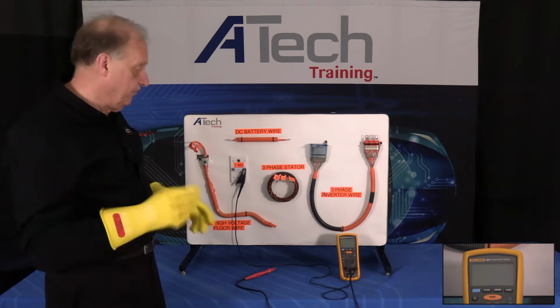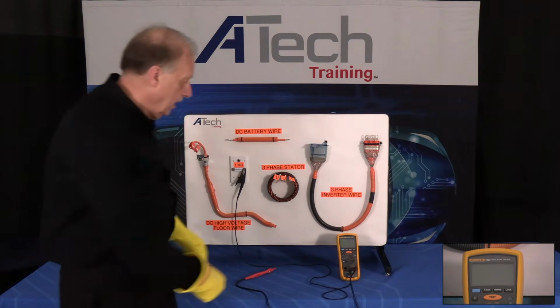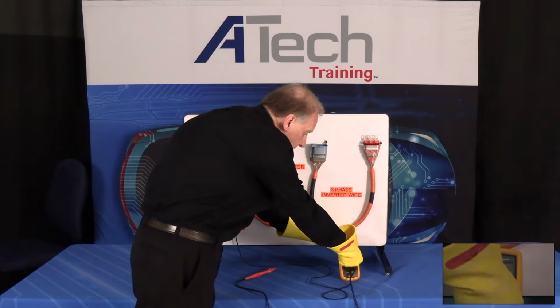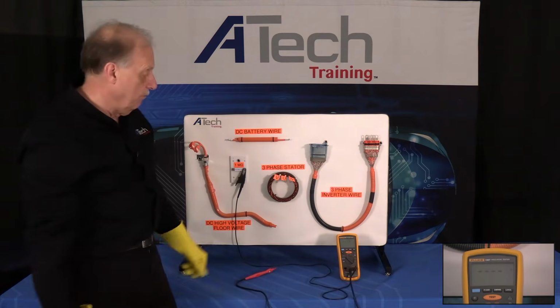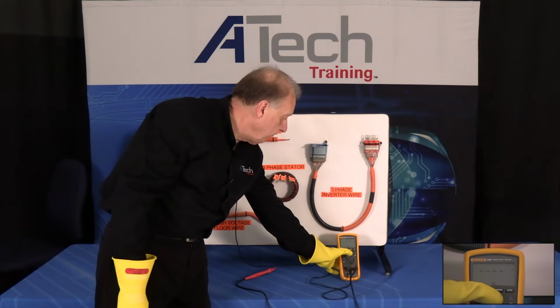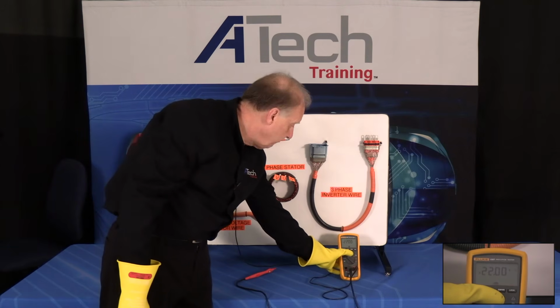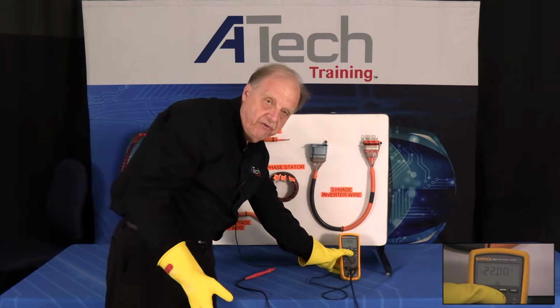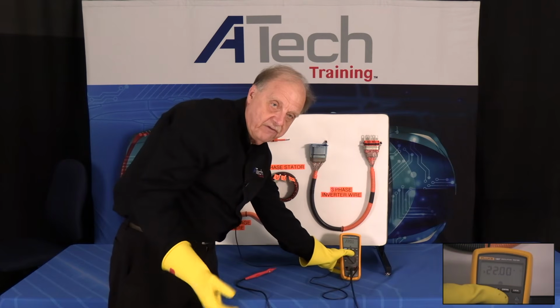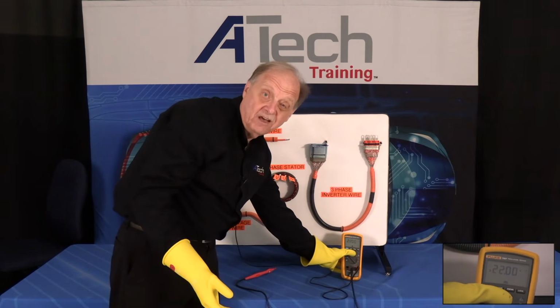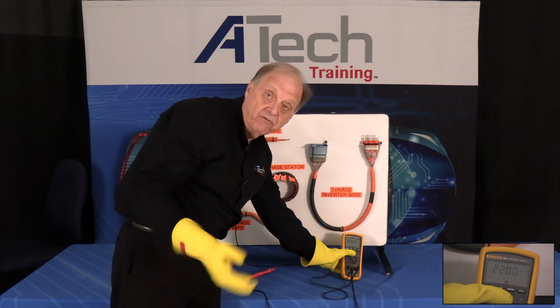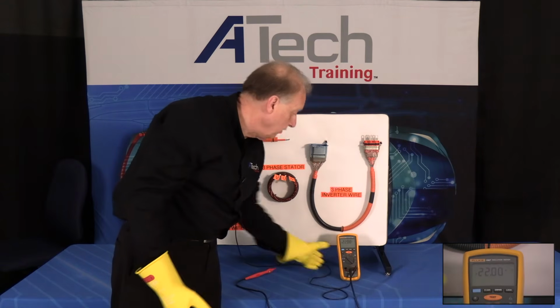Next thing we want to do is check the fuse in the system. To check the fuse, we put it in ohms, and you just want to hit test. When you hit test, you're going to look at it, it says 22. As the slide says, if it doesn't see this, it's actually going to say that the fuse is bad, it'll say bad fuse. So we've got everything looking good there.